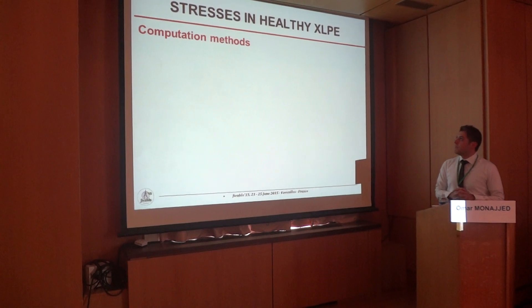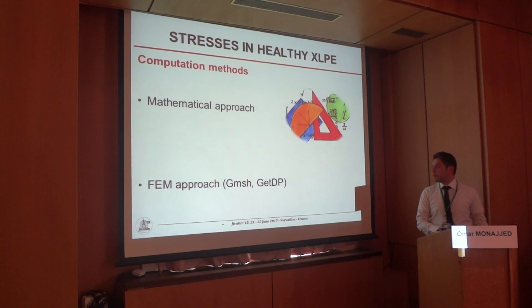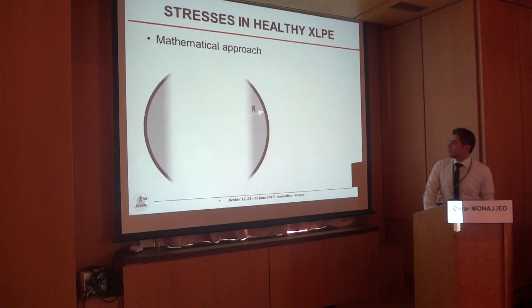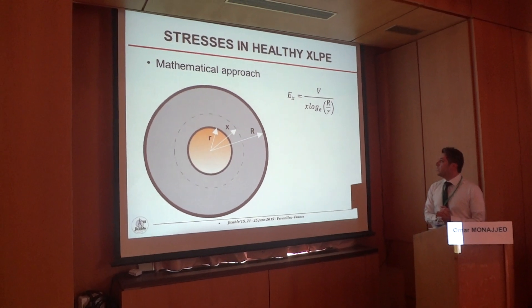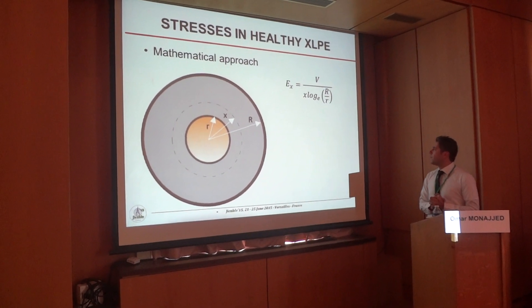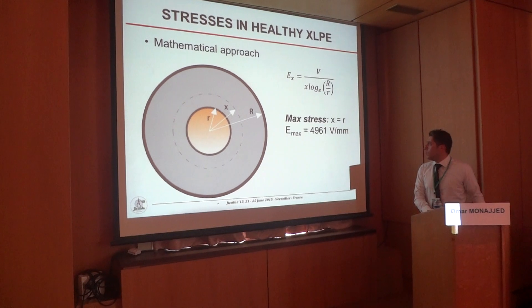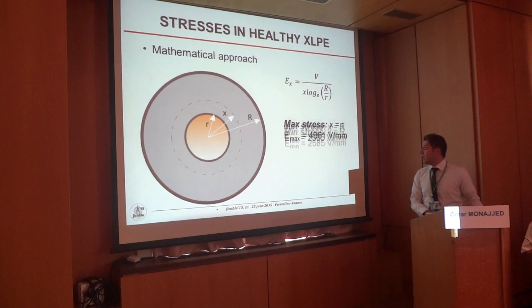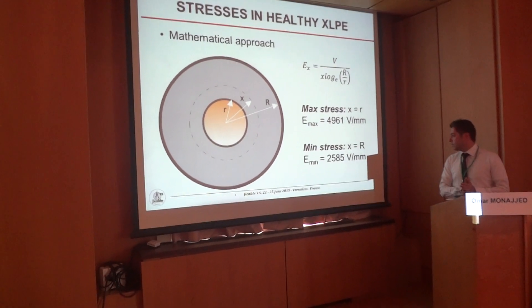For stresses in healthy XLPE, we have two computation methods. The first is the mathematical approach, and the second is the FEM approach using Gmsh and GetDP software. For the mathematical approach, we use the standard formula where V is the phase-to-ground voltage, x is the distance from the conductor to the desired point, R is the radius above insulation, and r is the radius under insulation. We get maximum stress when x equals r: E_max equals 4961 V/mm. And we get minimum stress when x equals R: E_min equals 2585 V/mm.